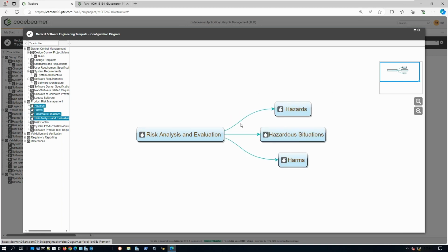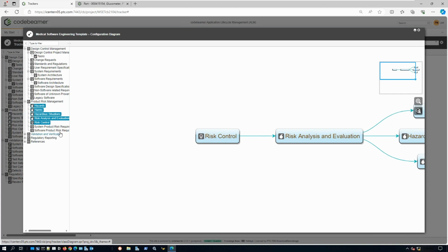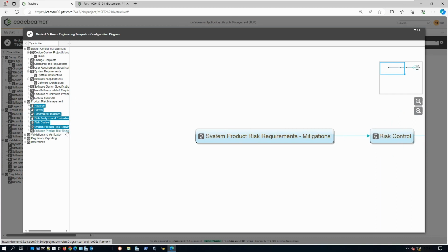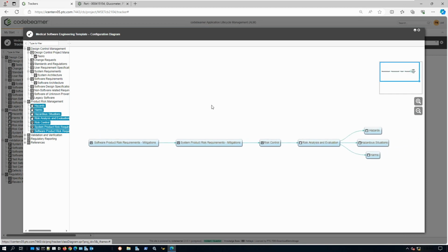Okay, so these within maybe a medical device ideology will basically be a standalone tracker where we can have a repository of information that's used across multiple different projects. Okay, from there we can impose certain risk controls as well as mitigations, okay, to minimize those risks. So while this traceability shows a software-based approach, this can also be expanded to electrical and mechanical systems, okay?